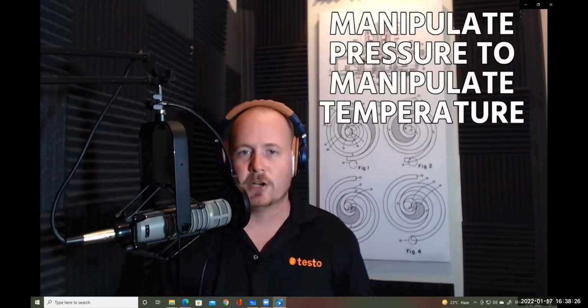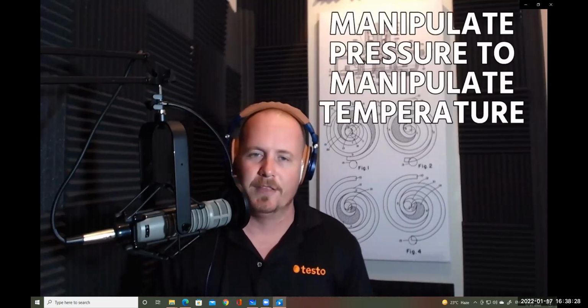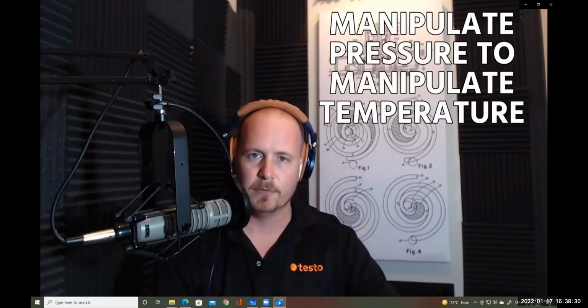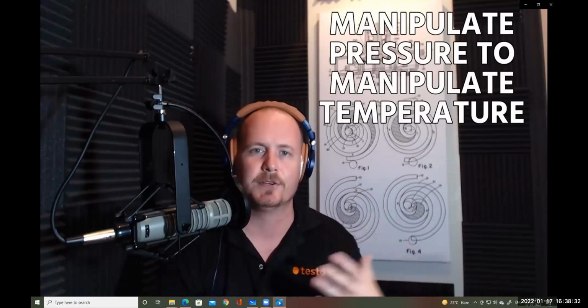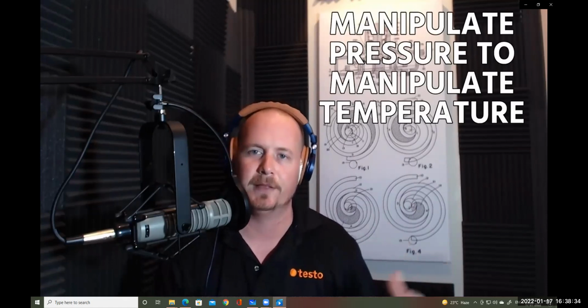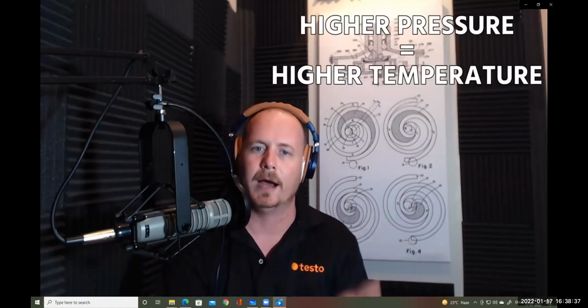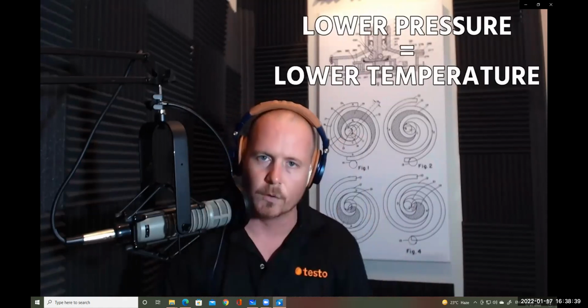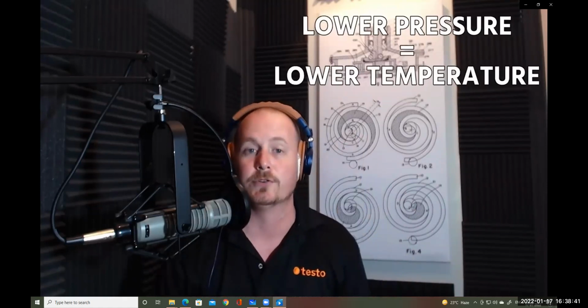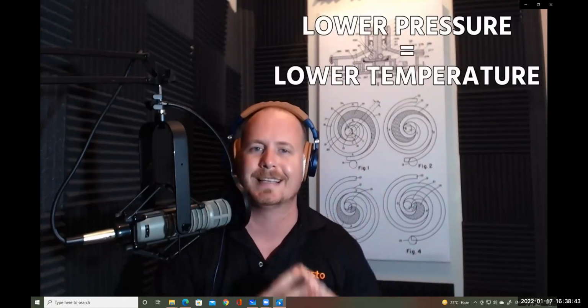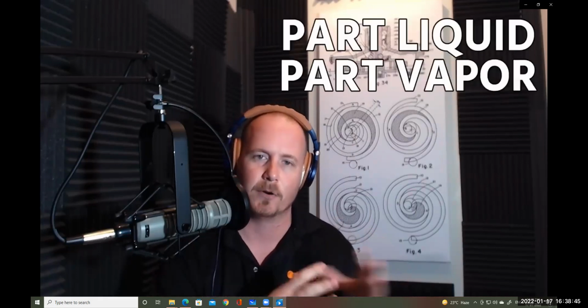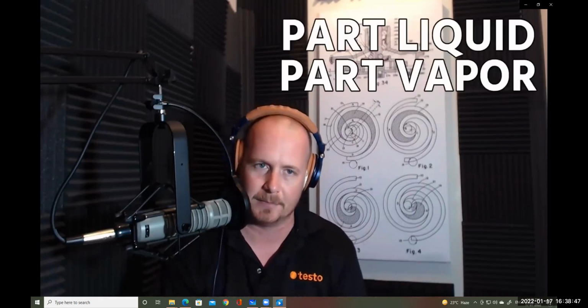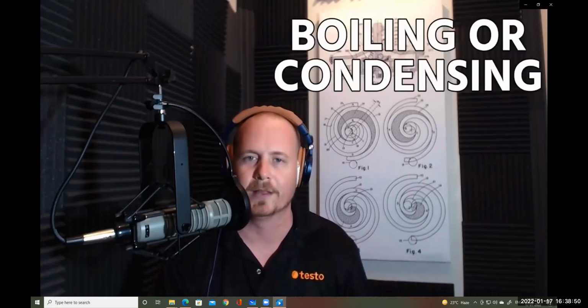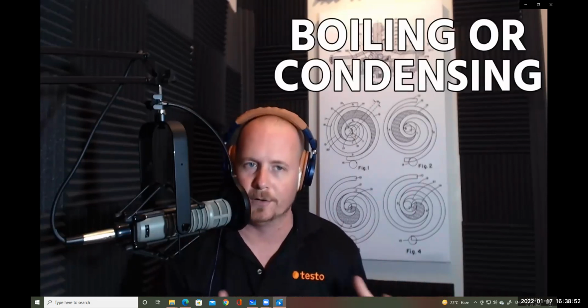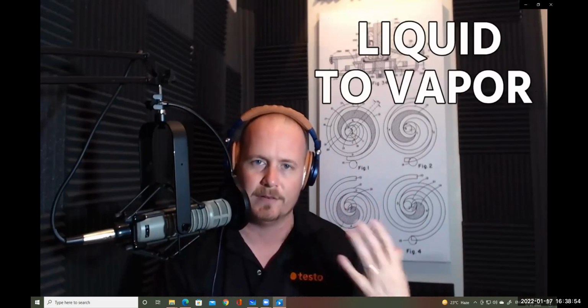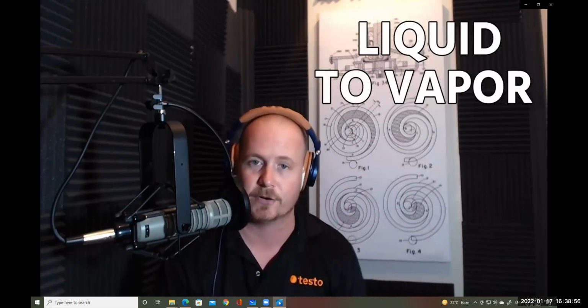So by manipulating the pressure, we can manipulate the temperature of that evaporator coil. You imagine this boiling refrigerant moving through it. We can manipulate the temperature at which it's changing state by manipulating the pressure. Like we talked about before, higher pressure equals higher temperature, lower pressure equals lower temperature. And that's also true when you're dealing with what we would call a saturated refrigerant. That means that it's part liquid and part vapor together at the same place at the same time, otherwise known as boiling or condensing. Inside the evaporator coil, it's boiling. It's changing state from liquid to vapor, like I said, fairly rapidly as it circulates through the system.